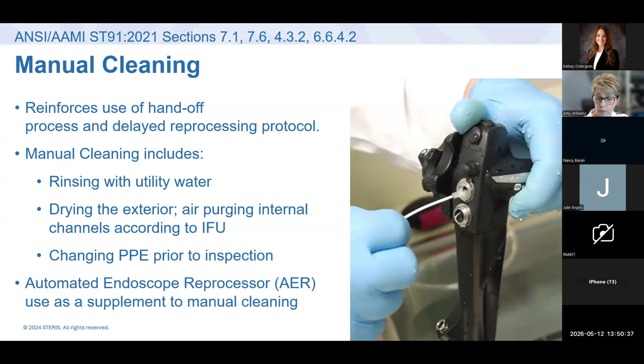Cleaning verification. So visual inspection inside and out, making sure that it is in fact clean. And then cleaning verification testing is whatever type of chemical test you want to use to ensure that residual contaminants have been removed. Lots of different things out there, protein, carb, hemoglobin, ATP, they don't specify. It's up to you to decide what you want to use for your facility. Whatever you decide should be in your policy, and your staff should be trained on it. And it should be used consistently.